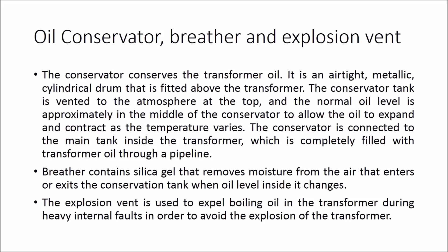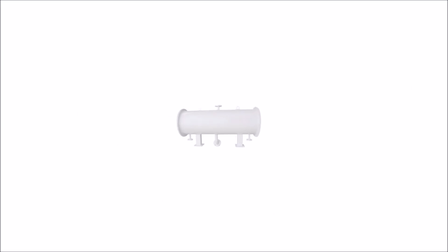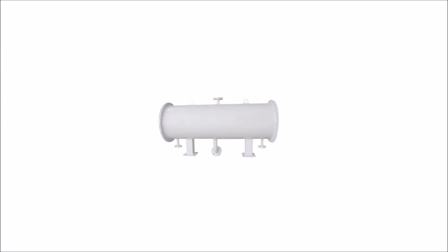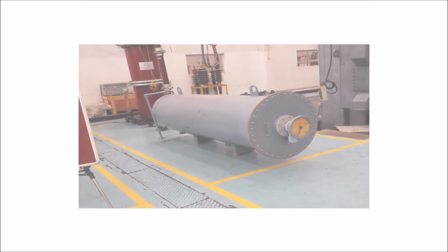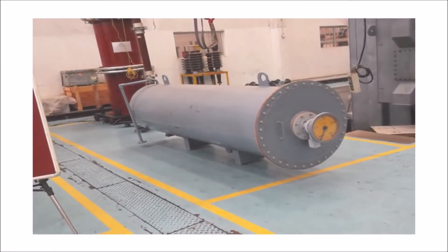The conservator conserves the transformer oil. It is an airtight metallic cylindrical drum fitted above the transformer. The conservator tank is vented to the atmosphere at the top, and the normal oil level is approximately in the middle of the conservator to allow the oil to expand and contract as temperature varies. The conservator is connected to the main tank inside the transformer, which is completely filled with transformer oil, through a pipeline.